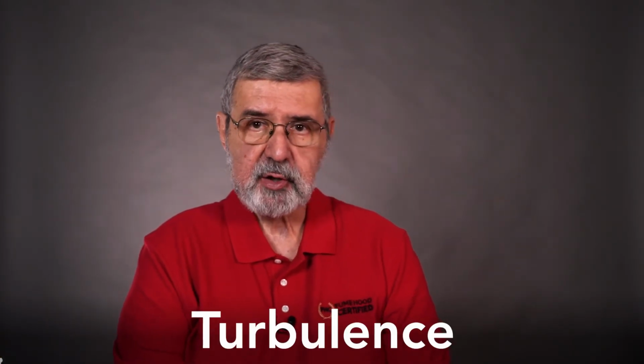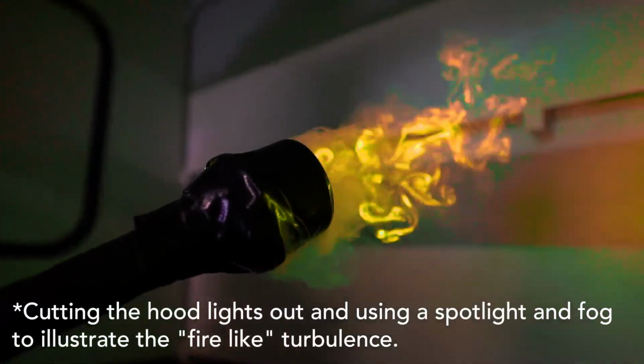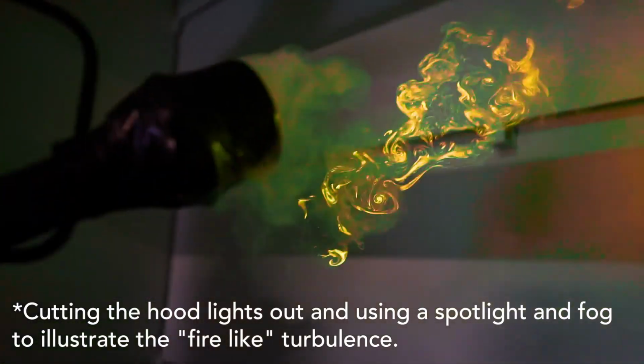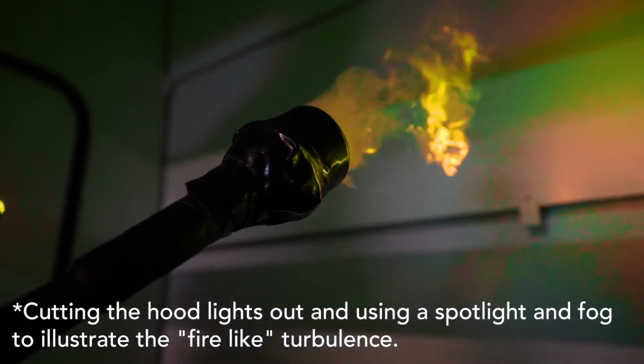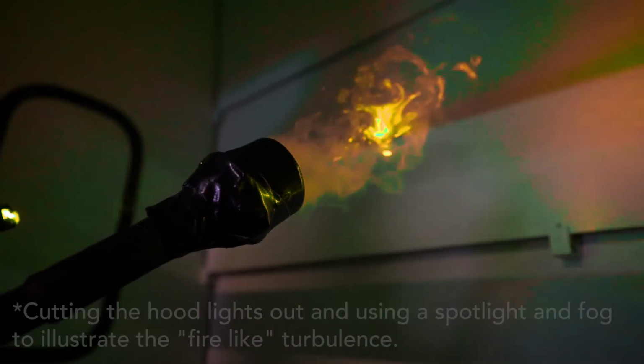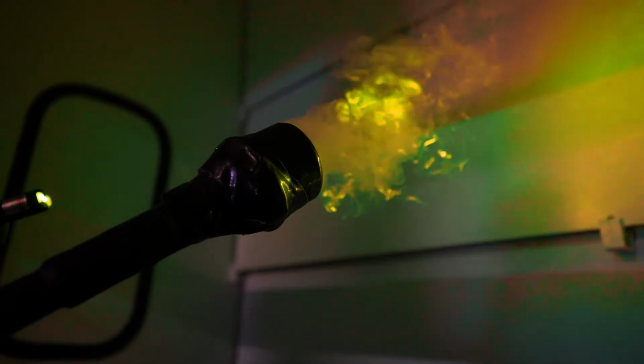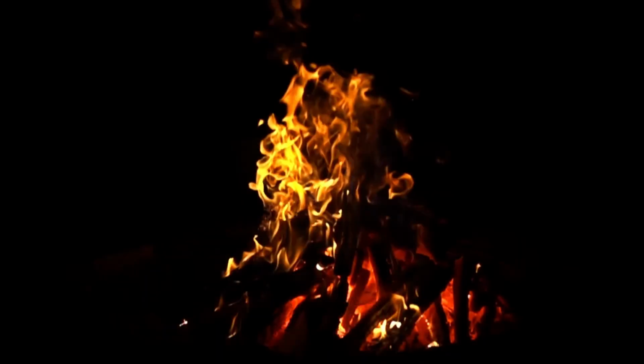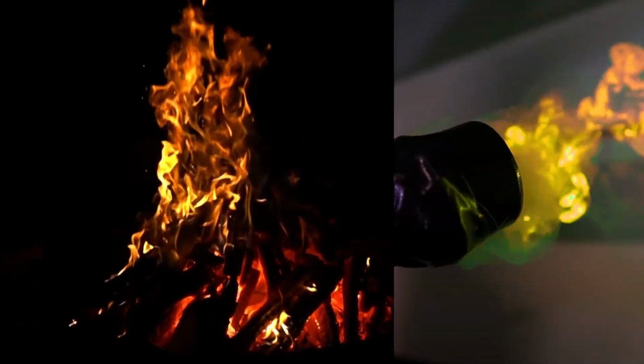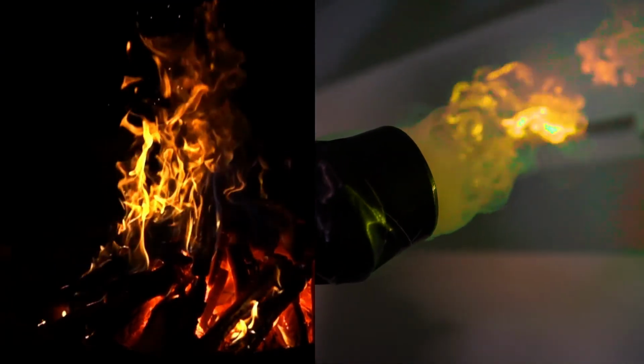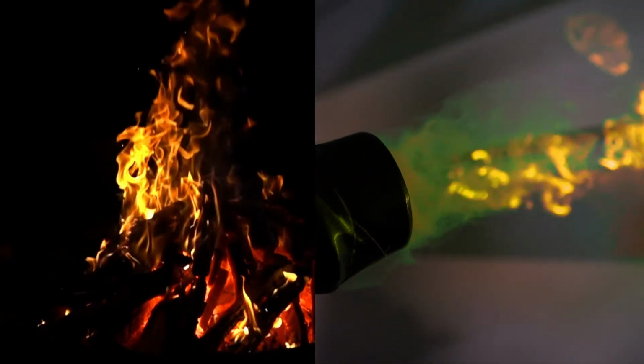Fume hoods are very turbulent devices. If you could see airflow and it were reddish orange, it'd look very much like the flames of a fire. Pressure changes are continuous, and that impacts the airflow. Much like a campfire, no 2 seconds are exactly the same. It is as if the fume hood were breathing.